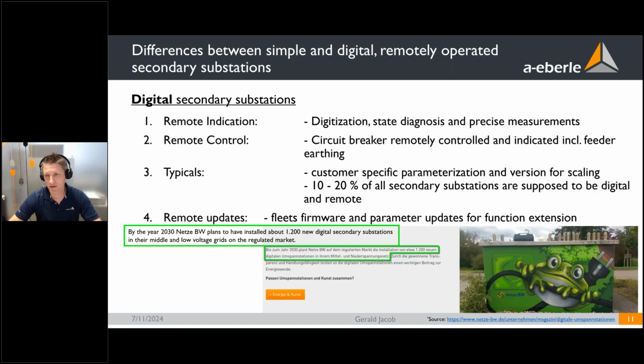So these were the simple, analog secondary substations, and here we have the opposite, digital secondary substations. They have 4 main topics. First one, remote indication. So not only precise measurements, this is the most important one, but not only precise measurements out of these very important secondary substations are getting transferred to the central SCADA system and to a big data pool, but also a state diagnosis of the whole secondary substation is done. For example, door contacts, temperature of the transformer, temperature of the bushings, and so on.